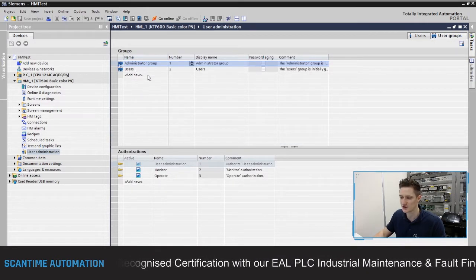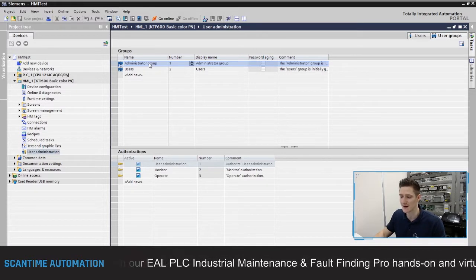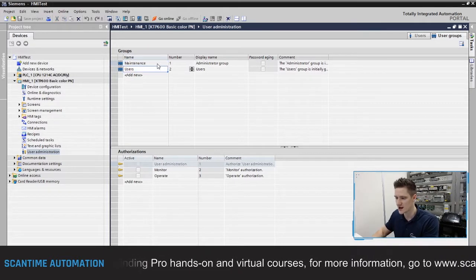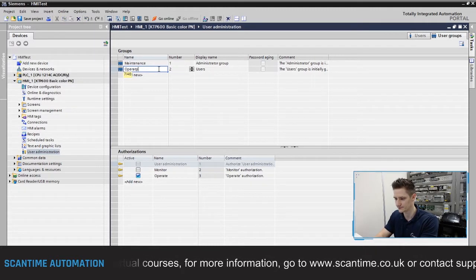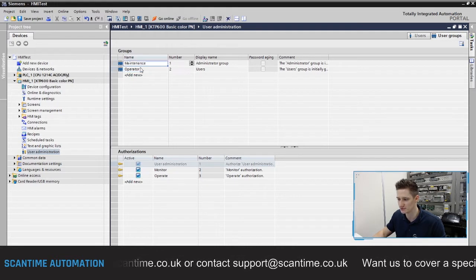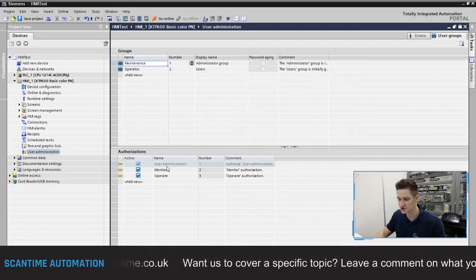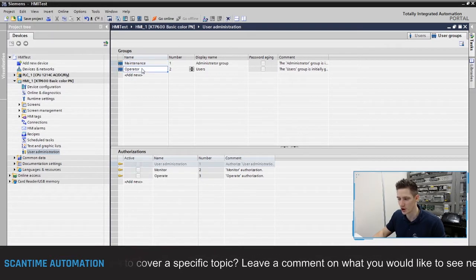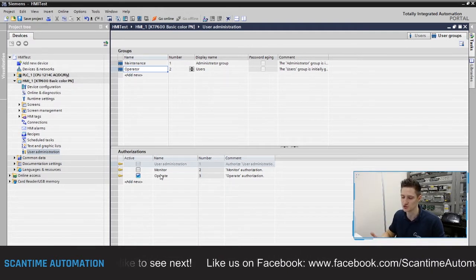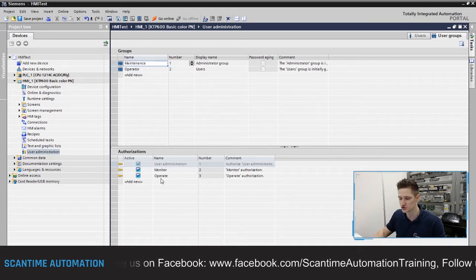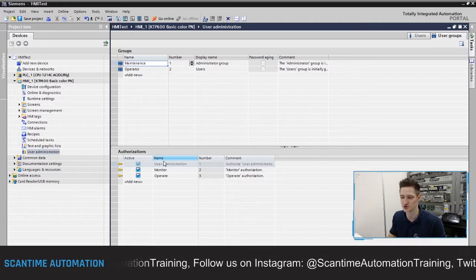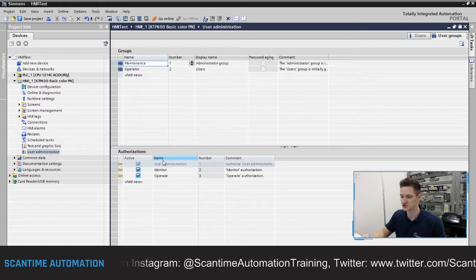I'm going to create two levels of security: Maintenance and Operator. I'll rename 'Administrator Group' to 'Maintenance' and 'Users' to 'Operator'. You'll notice the authorizations at the bottom change when you switch between groups. For Maintenance, they have access to the entire HMI — User Administration, Monitor, and Operate. For Operator, they simply have Operate. These authorizations can be changed to restrict users as needed.